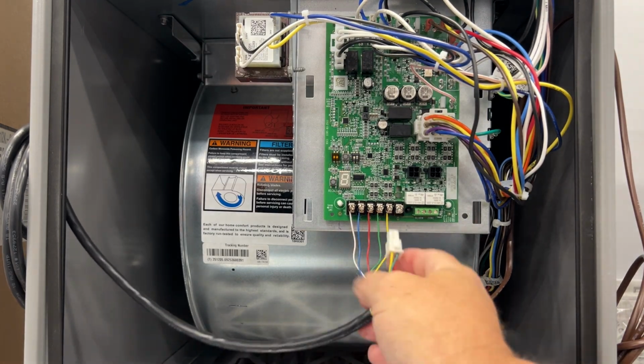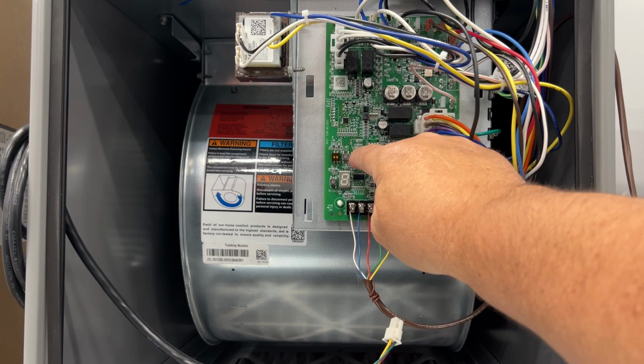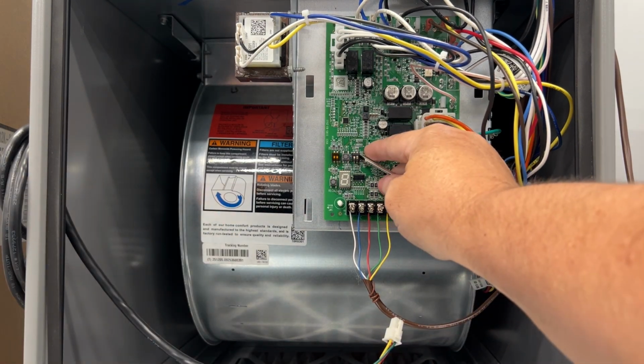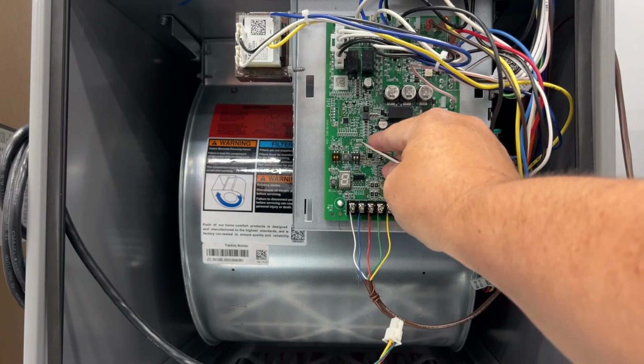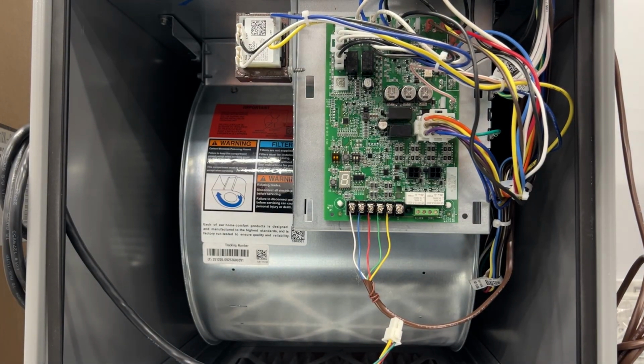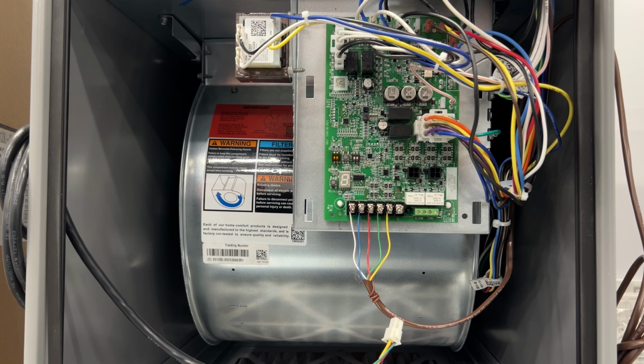All right. So what happens if you don't put a sensor in at all? In this case, you would have the dip switches both down, and let's say you started up the furnace and you didn't put the sensor in at all. Here comes the fan. And of course, you see an error code comes up. This time you'll get 2 error codes, 154 and 155. That means it should have sensors and it should be set up, and it doesn't find the sensors.